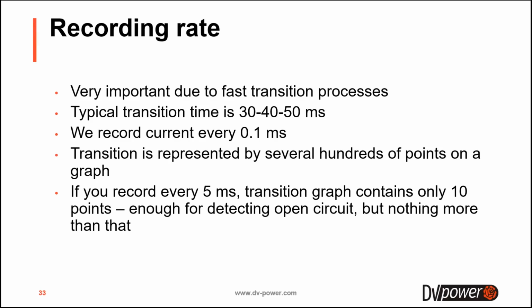Okay. Another thing that is very important for DVtest is recording rate, or how fast we record the DVtest. I mentioned at the beginning of the presentation the typical transition time is 30, 40, 50 milliseconds. So it's a very, very quick and very fast process. And because of that, you need to record this DVtest with a very high sampling rate. What we at DVPower do is we record this current every 0.1 milliseconds. That means the transition, that zoomed part, if you remember, is represented by several hundreds of points on a graph.